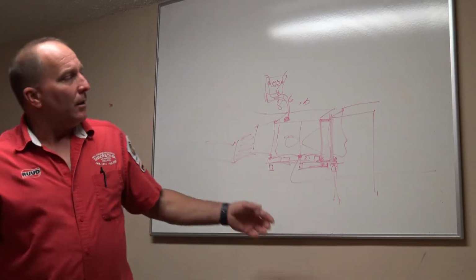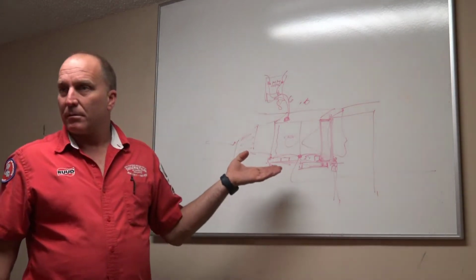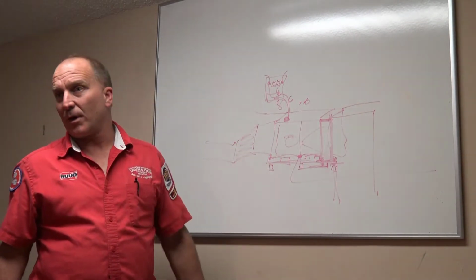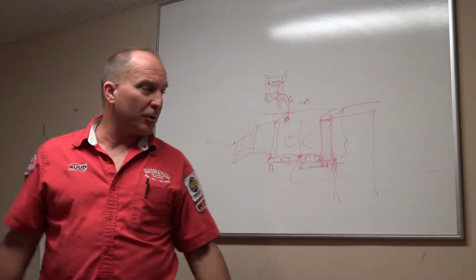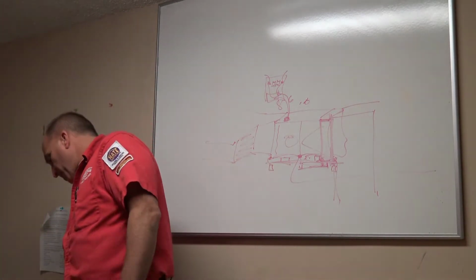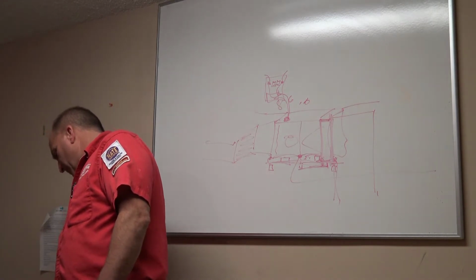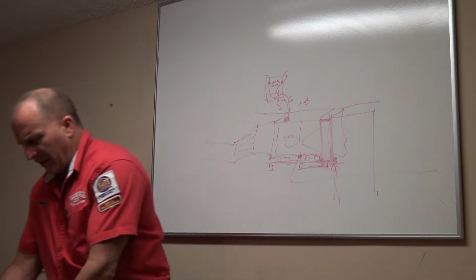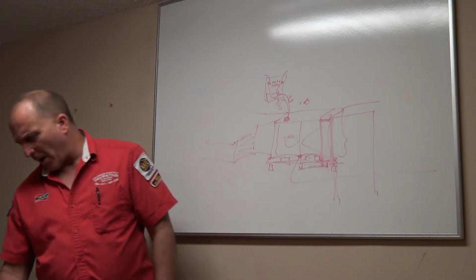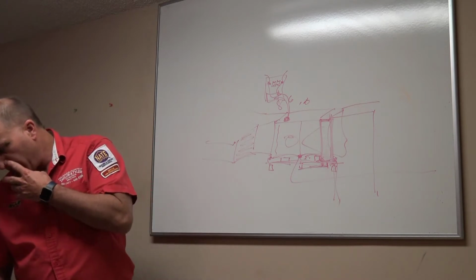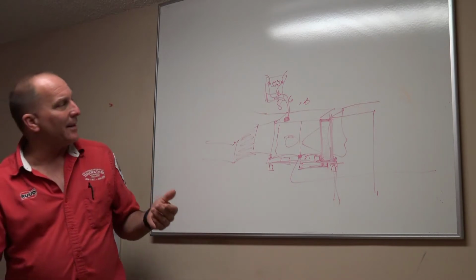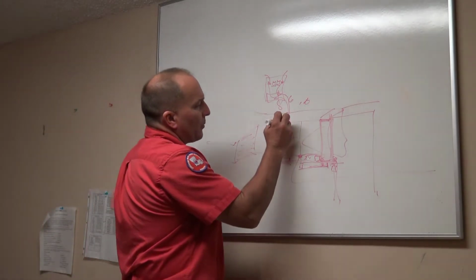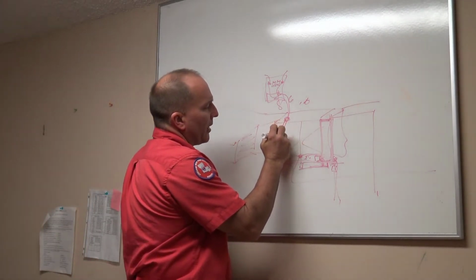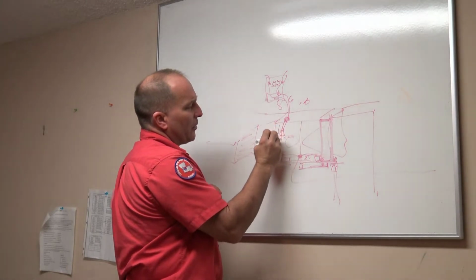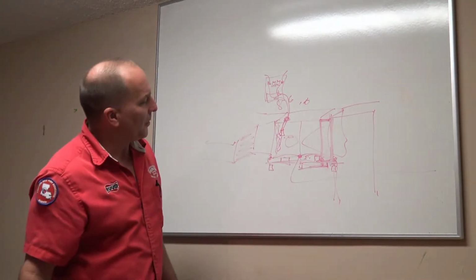Okay? You don't have a float switch. Should you have a float switch on every drain pan? Yes. Should you have a float switch on your main drain line? Yes. Okay, proper wire size, Romex connectors on, wires are secure, nothing is burned. Miswired, heating system does not work due to miswiring or either low or high voltage. Burn means the wires are burned, bad connections. So this right here goes into a breaker, okay? Here's your breaker right here, guys. Then this goes into your electric heat system and powers up your heating elements, right?